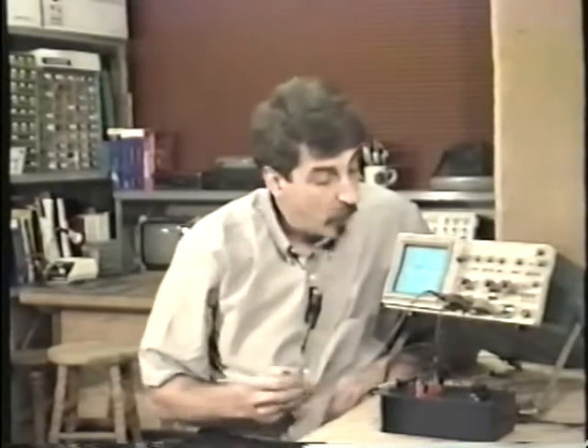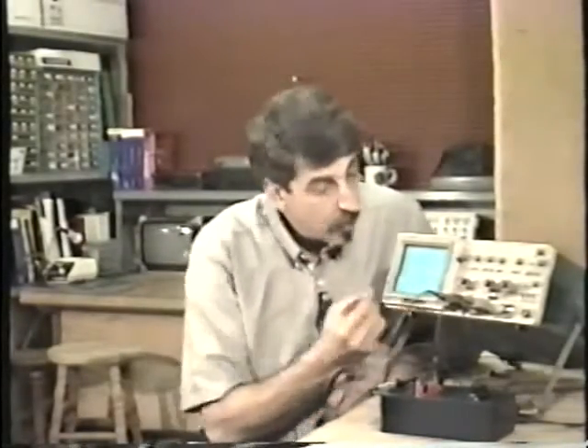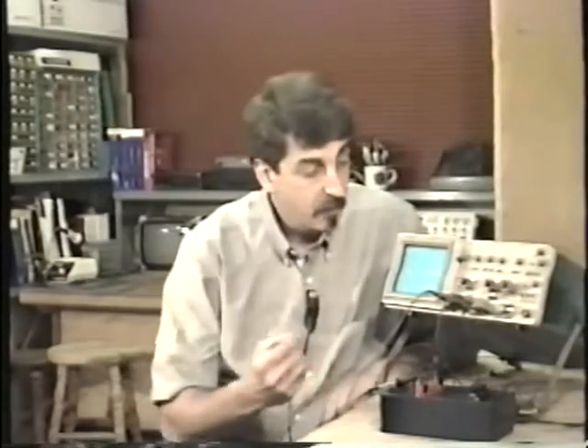The next step faster is in milliseconds. That's thousandths of a second. And it's 50 milliseconds per division. That's 50 thousandths of a second for the beam to move one horizontal division across the face of the graticule.